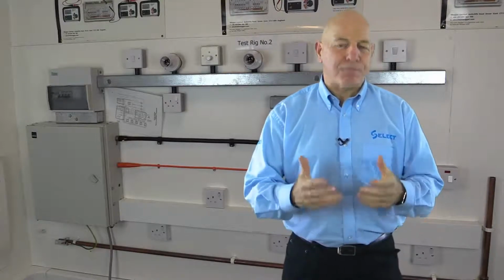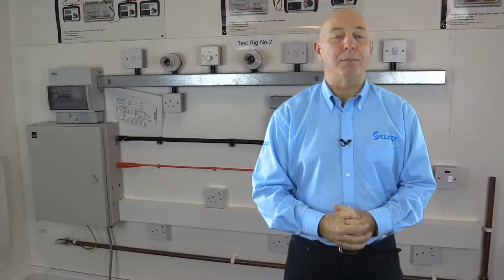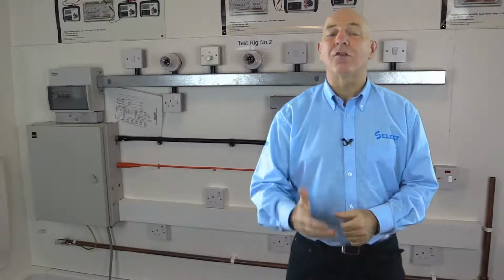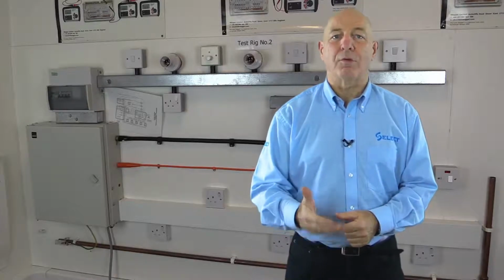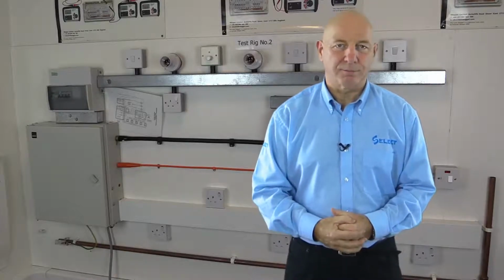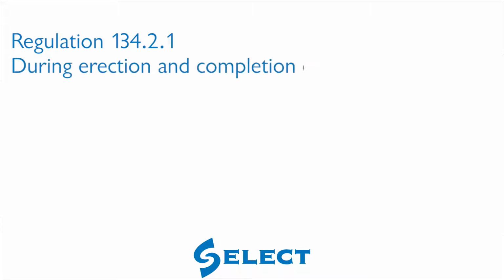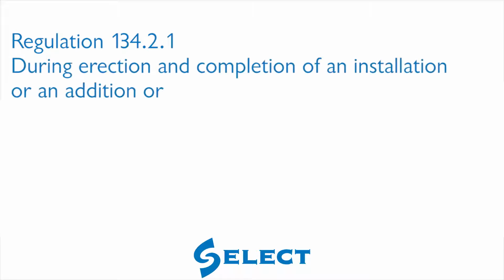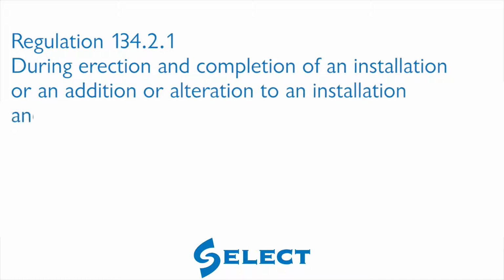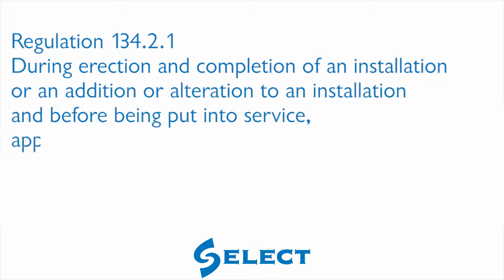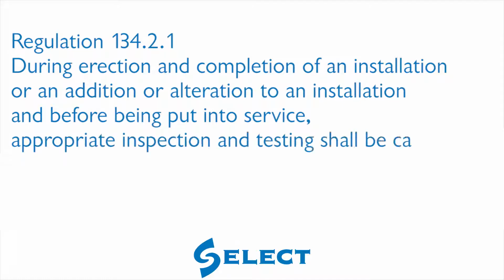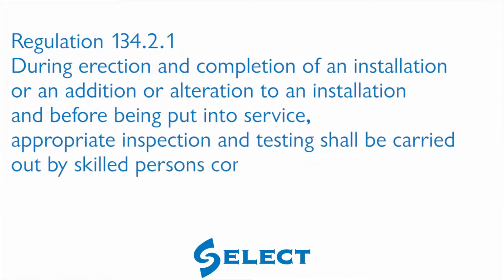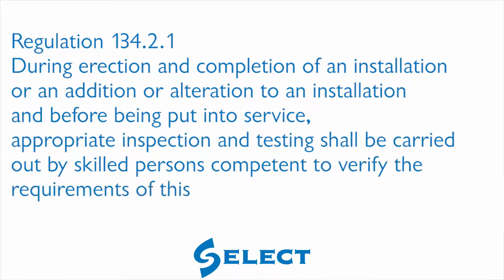You see, there's a fundamental requirement for inspection and testing in BS7671, which is the industry standard that provides the requirements for electrical installations. Regulation 134.2.1 requires that during erection and completion of an installation or an addition or alteration to an installation, and before being put into service, appropriate inspection and testing shall be carried out by skilled persons competent to verify the requirements of this standard have been met.